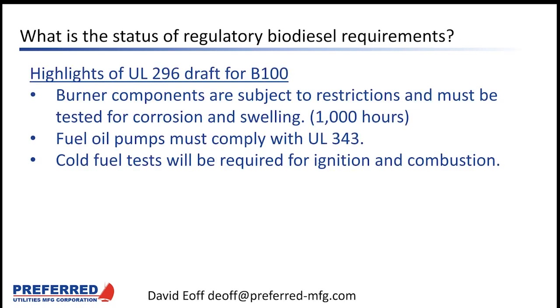So I thought that UL had only just submitted a draft for review of UL 2090 or UL 296, but it turns out they actually published it just a couple of weeks ago. So here are the highlights of UL 296 with respect to diesel firing. Burner components are subject to material restrictions and must be tested for corrosion and swelling, and it's a 1,000-hour test. The intent is to make sure burner manufacturers don't use any of the materials known to not play nicely with diesel, and require them to test all burner materials for longevity.